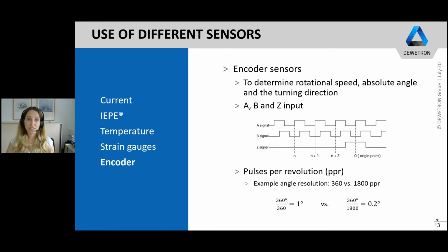For those encoder sensors, it is very important to consider that the hardware has a high enough bandwidth and input frequency in order to resolve the pulses per revolution, which are output by the encoder. The pulses per revolution also have an impact on the angle resolution, as you can see in this example here. For example, if you have an encoder which outputs 360 versus 1800 pulses per revolution, you get an angle resolution of 1 or 0.2 degrees.